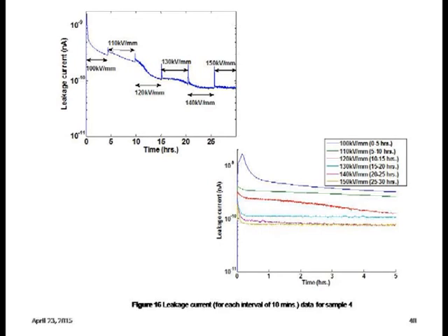So that's why LDPE has the highest breakdown strength and also several advantages, but see, it is not getting saturated even after 25 hours. Think about some 20-30 years then. We don't know what will happen. It may be continuously degrading or something happening, and after 2-3 years or 4-5 years, what will happen to the insulation is not known, right? So this is the important consideration. Ultimately, what matters is long-term performance. Initial performance may be better, but over a long run, whether the insulation will give the same performance or not is a question.